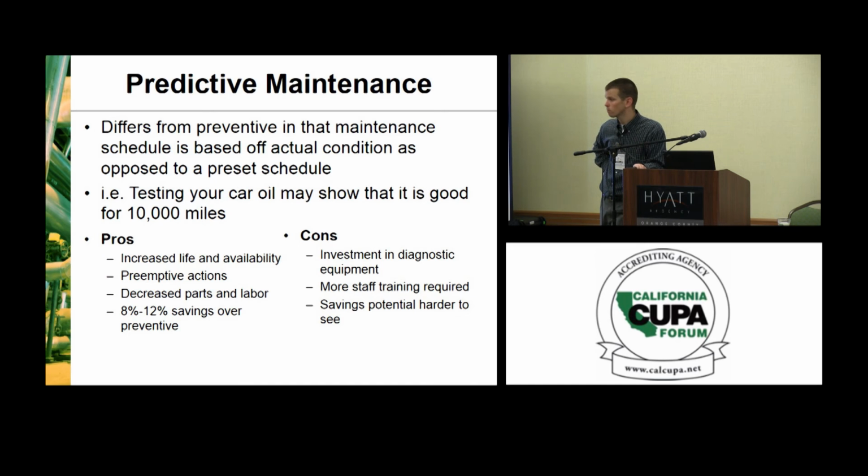Vibration analysis is another form of predictive maintenance. We don't just replace the bearings on a screw compressor just because 5 years have gone by. But what we would recommend maybe is they do vibration analysis on a regular basis so they can trend the condition of those bearings and pinpoint, okay, the bearing failure is going to start occurring around this time. Ultrasonic thickness testing. We don't replace pipes just because they've been in service 20 years. A pipe that's been in service 20 years might be in horrible condition, but it might be in great condition. Right? I mean, it could be either way, but doing ultrasonic testing on the pipe gives us an idea, more information, right? So predictive maintenance is, I believe, the direction I'd like to see the industry go in, adopting more predictive tools.